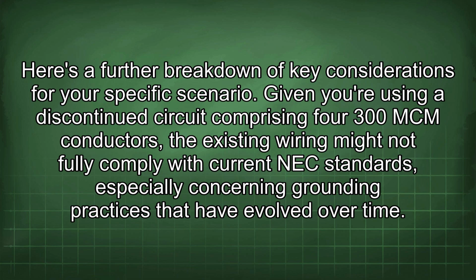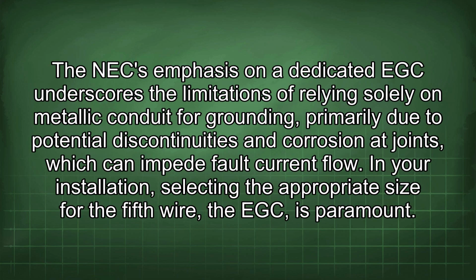Given you're using a discontinued circuit comprising 300 MCM conductors, the existing wiring might not fully comply with current NEC standards, especially concerning grounding practices that have evolved over time. The NEC emphasis on a dedicated EGC underscores the limitations of relying solely on metallic conduit for grounding, primarily due to potential discontinuities and corrosion at joints, which can impede fault current flow. In your installation, selecting the appropriate size for the fifth wire, the EGC, is paramount.